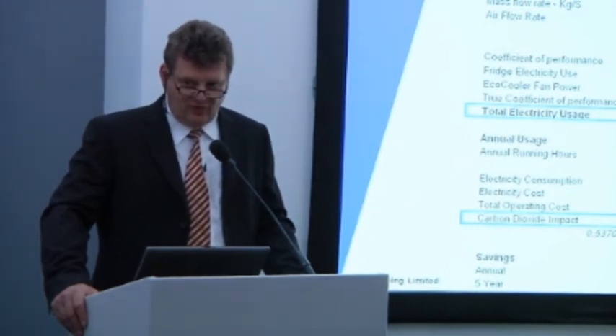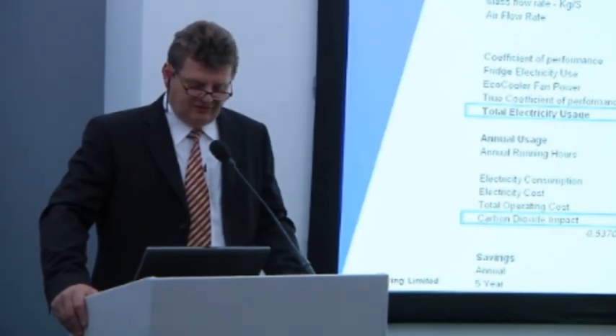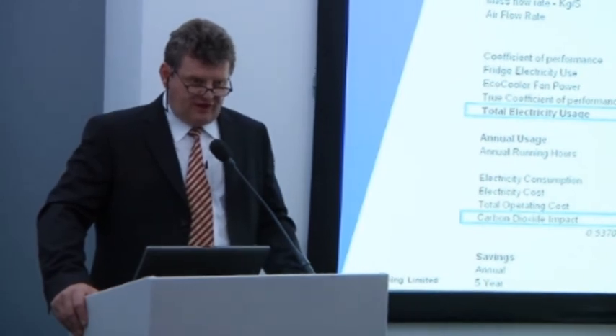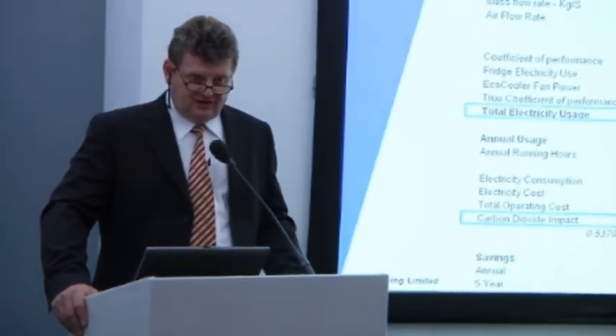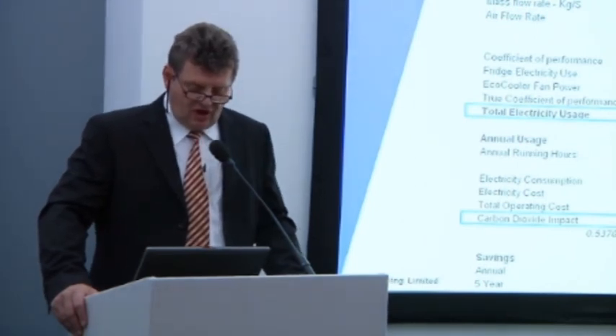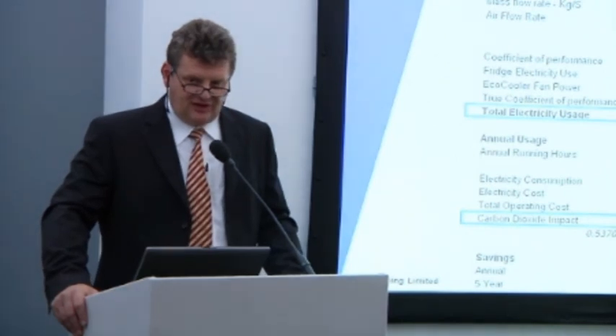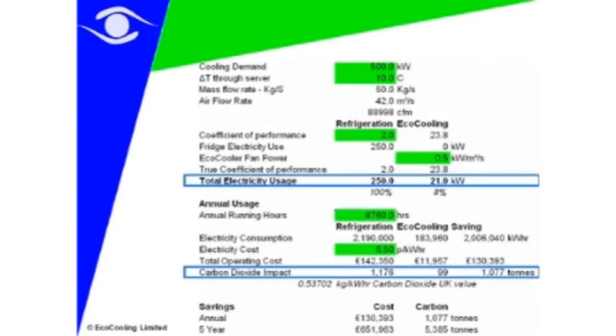There are 8,760 hours in a year — we can't get away from 24/7, 52 weeks, a lot of hours. The M247 project, if they had gone down the existing conventional route, would have been using over 2 million kilowatt hours of electricity per year; the Eco Cooling system would require less than 200,000. At six and a half pence per kilowatt hour, their annual running costs for the conventional system would be £140,000 compared to just over £10,000 for the Eco Cooling system, with a potential environmental benefit of saving over a thousand tons of carbon as well.